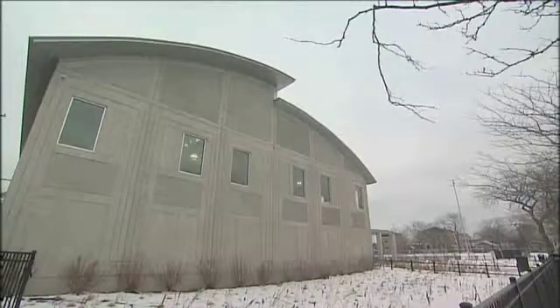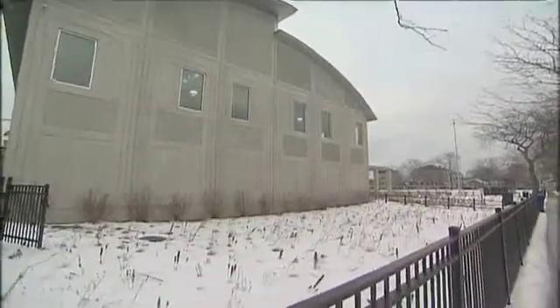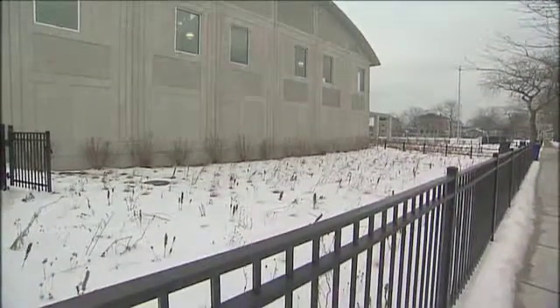A lot of people are like, oh, what's this geothermal? What's it look like? Where is it? You cannot actually see it because there are about 12 different wells that are bored into the ground that go down about 500 feet, and they're only about 3 inches in diameter, and what that allows us is to have those 2 pipes that go down and do the heat exchange and come back up. And once they're installed, you just put regular plantings right over it.